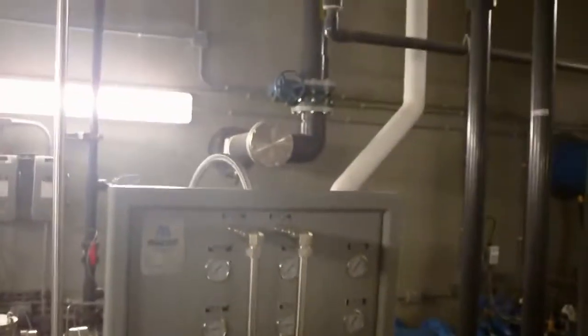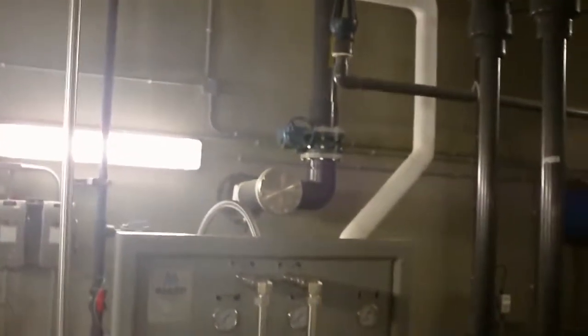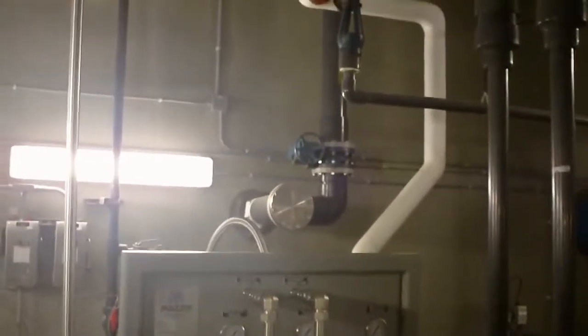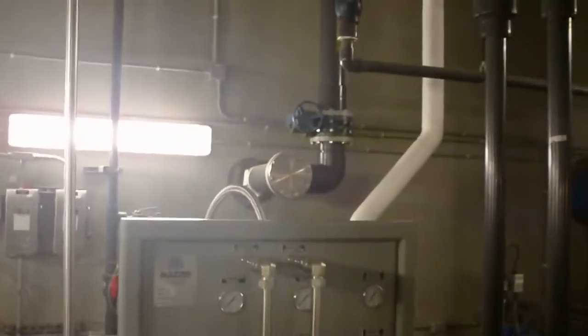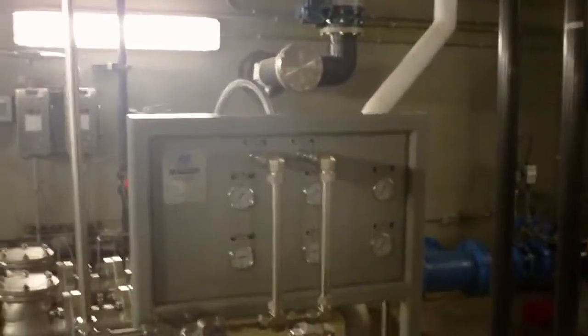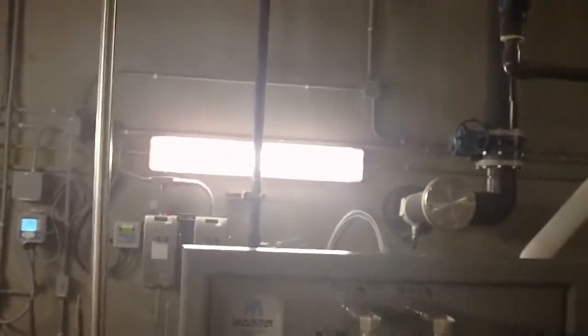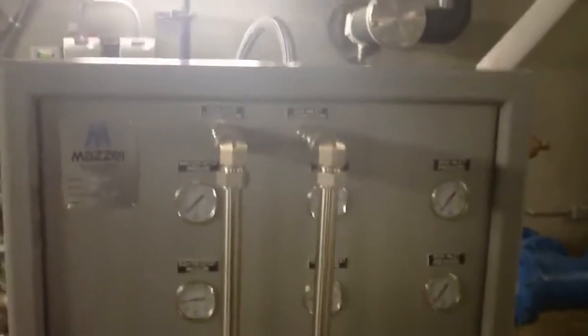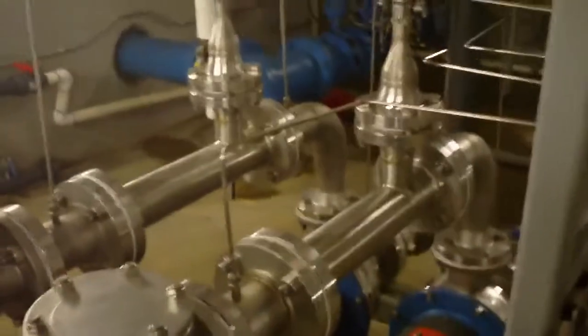We are in the basement of the North Burley County Water Treatment Plant, part of the South Central Water System. We are going to be looking at the dissolution system for the ozone, a system made by a company named Mazzei Injector Company. You'll see the front of their panel has all the gauges required to set up the system to maintain the right pressures across the two Venturis that you're looking at right now.